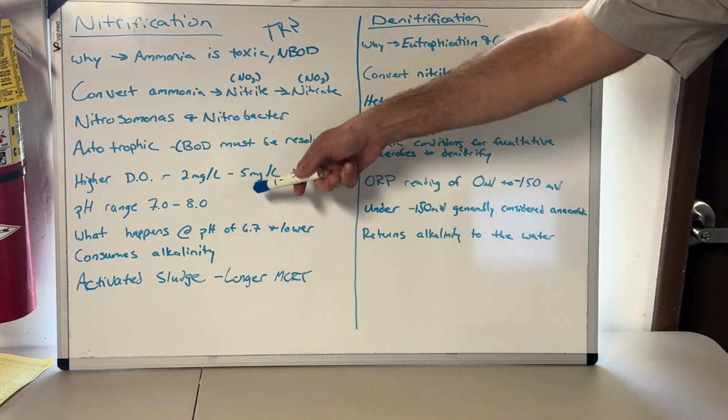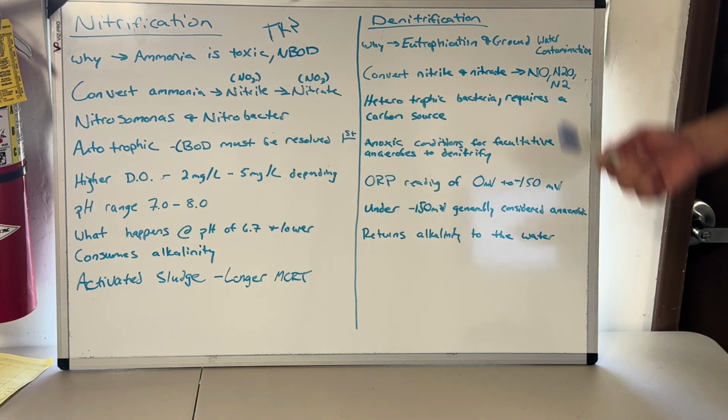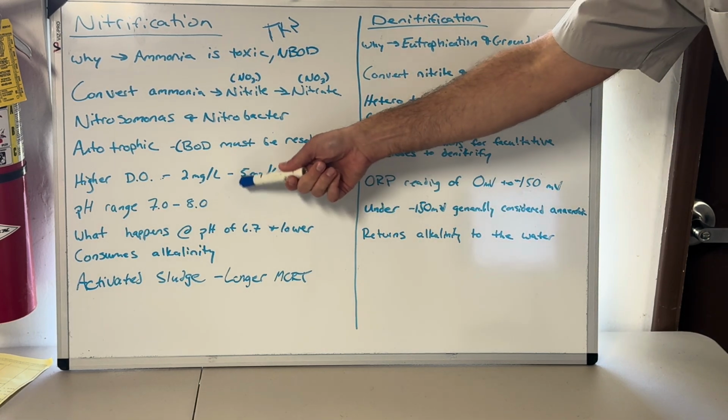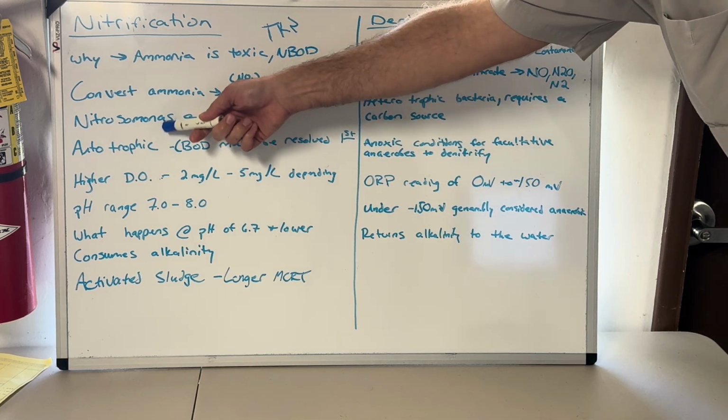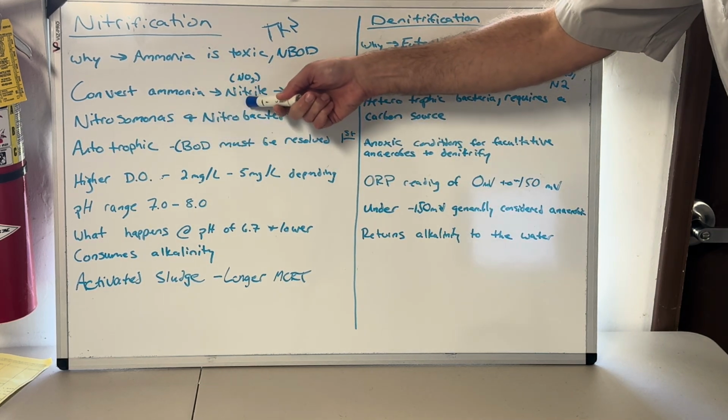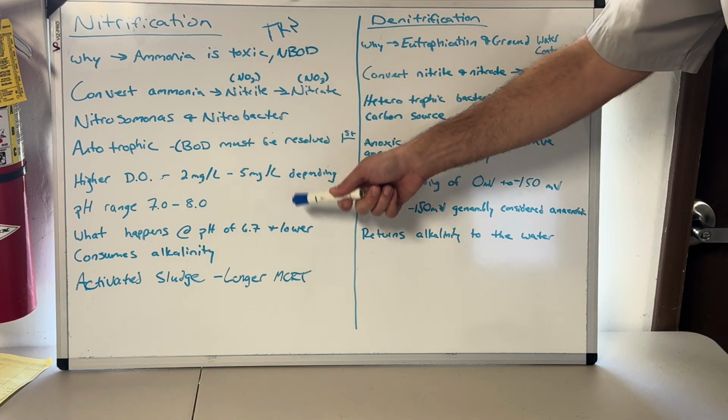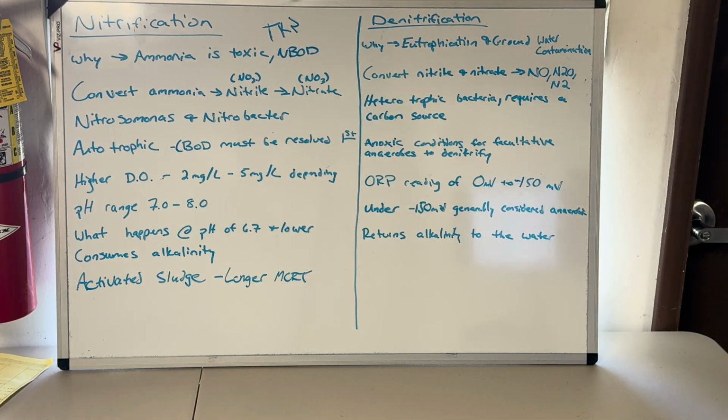So you may have a 4 in your aeration basin, and you're saying, hey, all good, I got my oxygen. Why am I in nitrite lock? There's only enough activity where we're getting here, but we're not getting here. What's going on? Check your pH. You might not be in the place you think you're at.